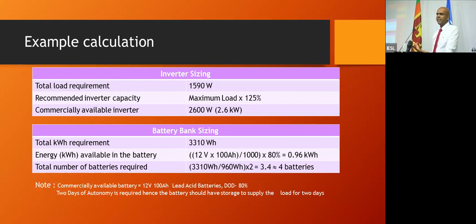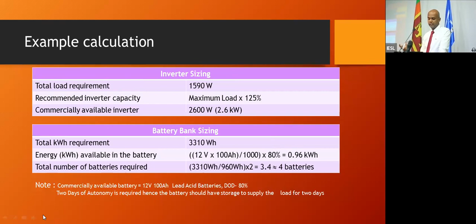Then you get the number of batteries you need. Let me see if I've put days of autonomy here. Yeah, here I've multiplied it by 2, so that in case we have 2 rainy days, we've oversized the battery so it won't be fully discharged. In Sri Lanka you don't normally get 2 continuous days of rain, unless it's today and yesterday. But this is just theory, so you understand that when you size a battery, size it for days of autonomy or a rainy day. This is how you typically size a battery system for off-grid.